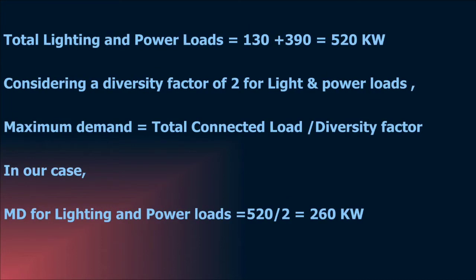Coming to the lighting and power loads, the lighting load is 130 kilowatt and the power load is 390 kilowatt. The total lighting load and power load is 520 kilowatt. We are considering the diversity factor of lighting and power loads to be 2. So the maximum demand of the lighting and power load will be 260 kilowatt.